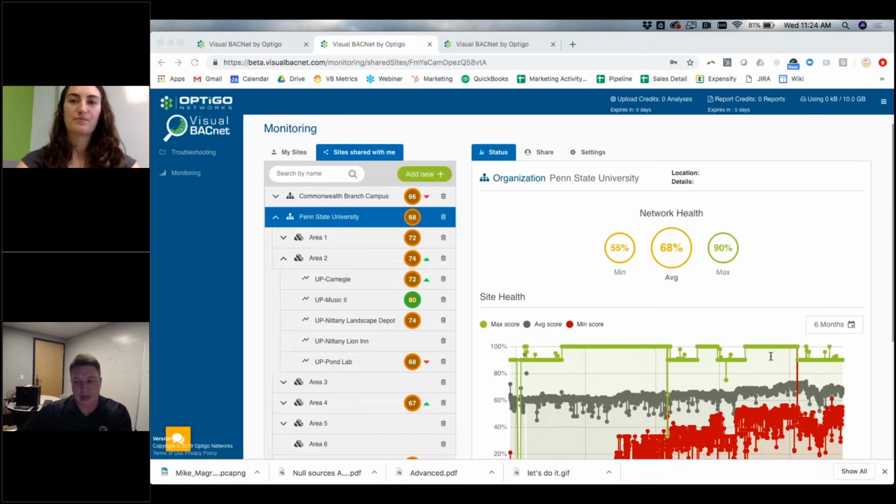And have them help us try to maintain these, because we get these one-off construction jobs where they're doing a VAV in one room, and so they didn't do a full project around that. They just went in, added the VAV, and did what they did, and maybe not changed out sensors and some other things, and all of a sudden we're getting a ton of noise from that particular device. Being able to have that data and be able to say, hey, look, you guys did something exactly at this time frame. What did you do? Or who was working in the building in that time frame? We need to know what they did so we can undo it or put it right so that there's not an issue.